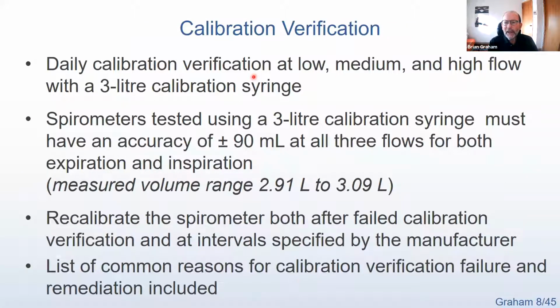Now, the daily check for calibration verification is done at 3 different flows, a low, a medium, and a high flow rate, with a 3-liter calibration syringe. This gets us not only the verification of the volume accuracy, but it also tells us that it's behaving linearly, that we can get this accuracy at low and at high flows. If we use a 3-liter calibration syringe, we have to be within 90 mL, and we do it for both expiration and inspiration. And we want to see all of that being verified.